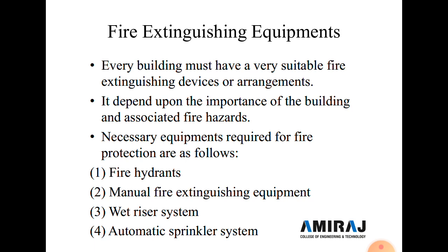Second is the manual fire extinguishing equipment. This type of equipment is most useful for extinguishing a fire when it has just started, but it is not as effective when the fire has spread. Portable fire extinguishers of CO2 type or foam type are used as fire safety equipment. The discharge from this type of extinguisher lasts only a short time, around 20 to 120 seconds. In small buildings, buckets of water, buckets of sand and asbestos blankets are normally kept ready at all times for extinguishing fire.